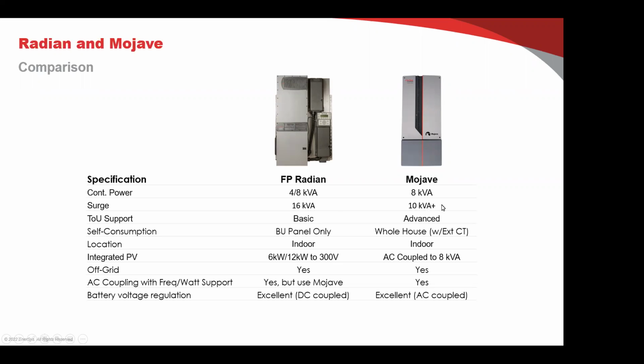I put a little plus sign after here because we do things a little bit differently with Mojave. We maintain the maximum current output. That 10 kW is 48 amps AC. And so when we have a surge device, we'll just make sure that 48 amps AC is there all the time. It doesn't go away. And we will allow the voltage to collapse while that's happening, which shouldn't be a problem for most surge loads. Most surge loads are current devices. They just need the current. And so we maintain that current.